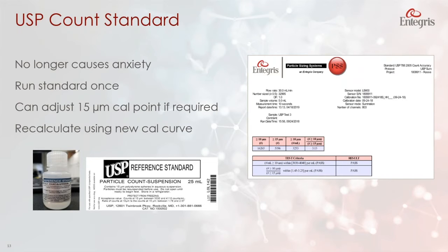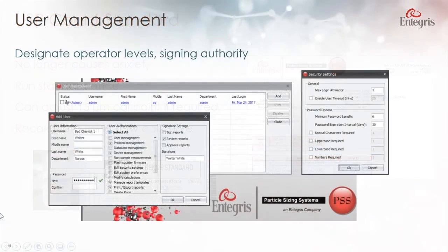So this is a sample where we need to make sure that we pass at the number of counts greater than 10 and the ratio between 10 and 15. We make this measurement now, and we can have this automatic report print out at the end to show us that we passed the requirements based on the certificate of analysis for the standard.